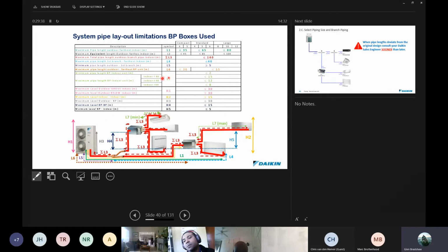Okay. I said to you I was going to talk about the BP boxes. Okay, one of the other measurements that I want to bring to your attention that comes up on this slide over here is the measurement L5 over here, which is 5 meters. You must have in any system 5 meters of piping before your first indoor ref net joint. Okay, very important to remember. We do come across installations where they try to put the first indoor ref net very close to the condenser. The minimum pipe run there is 5 meters for that.